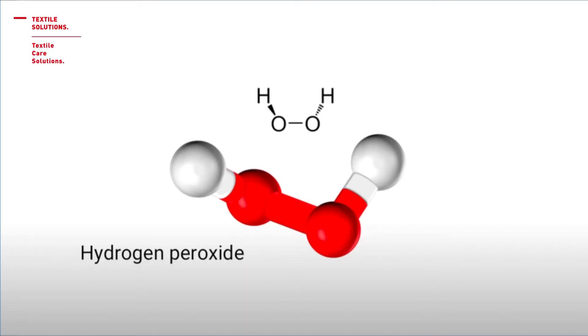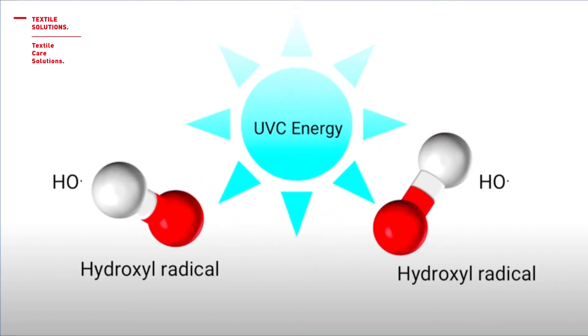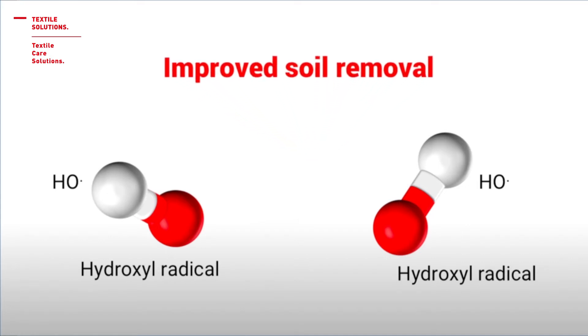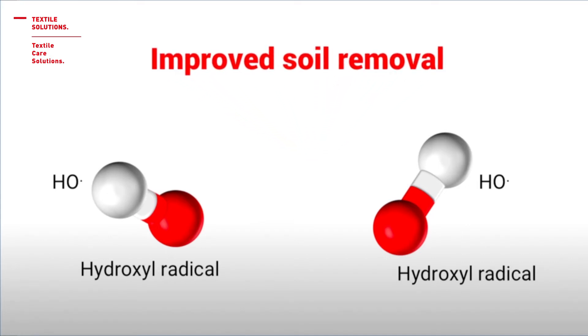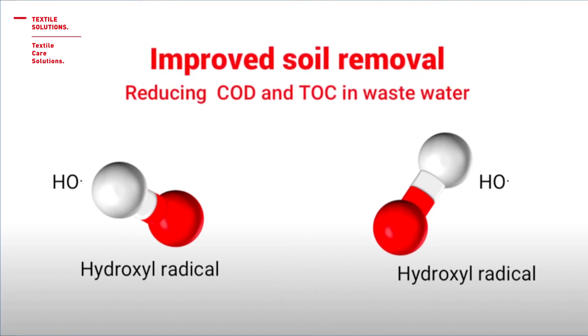That's the structural formula of peroxide. What happens with the peroxide under the influence of UVC power? It produces so-called hydroxyl radicals. Those hydroxyl radicals are often referred to as the detergent of the troposphere because they react with many pollutants, decomposing them through cracking until complete removal and elimination. Thereby we achieve a maximum of soil removal plus a significant reduction in COD and TOC.